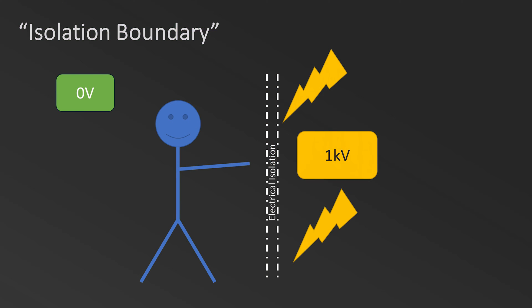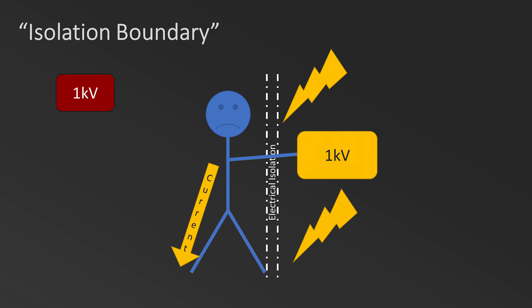Ultimately, when registering a device with a safety agency, it is up to that agency to ensure that the device under test is adequately safe. If achieving the separation distances listed in the safety standard is not possible due to space constraints, it is possible to run a series of high voltage tests that ensure that your design is still safe. These tests generally ensure that your device doesn't pass too much current from wherever the high voltage is to wherever the user can touch, and it ensures that the isolation does not ever break down or arc over whenever the highest reasonable voltage is applied across it.